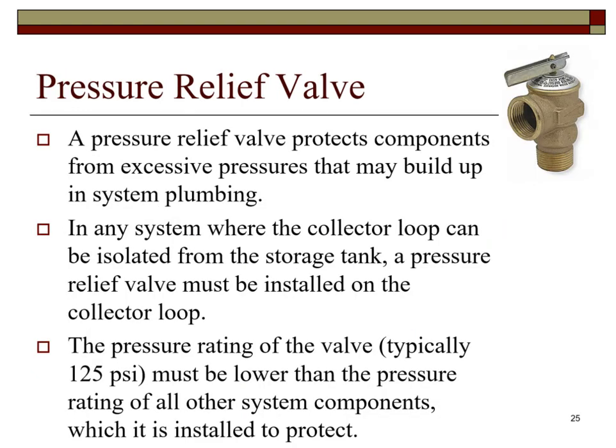A pressure relief valve protects components from excessive pressure that may build up in a system's plumbing. In any system where the collector loop can be isolated from the storage tank, a pressure relief valve must be installed on the collector loop. The pressure rating on the valve, typically 125 psi, must be lower than the pressure rating of all the system components which it is installed to protect.